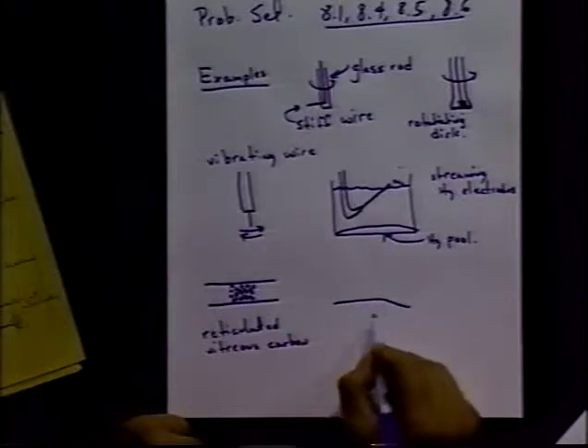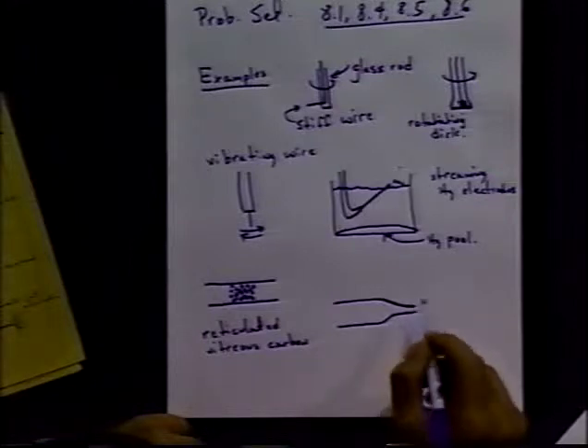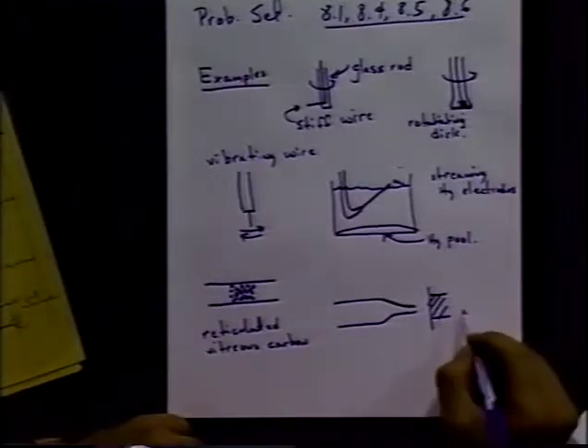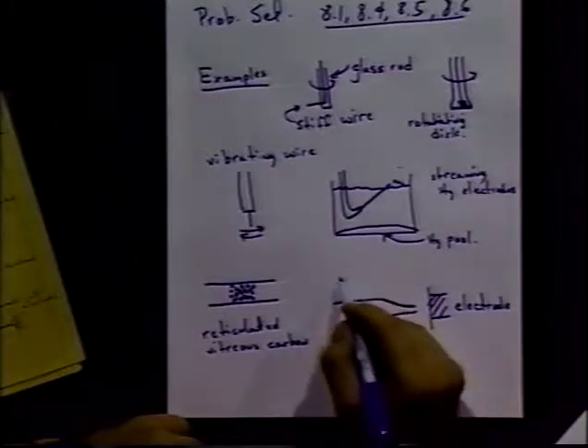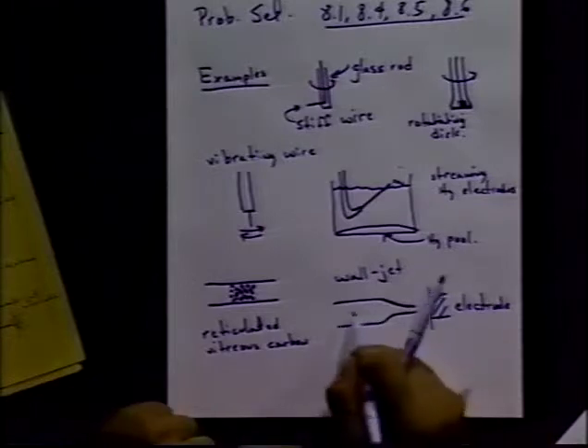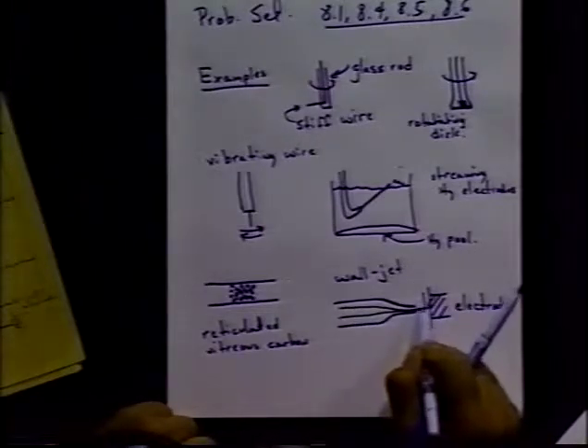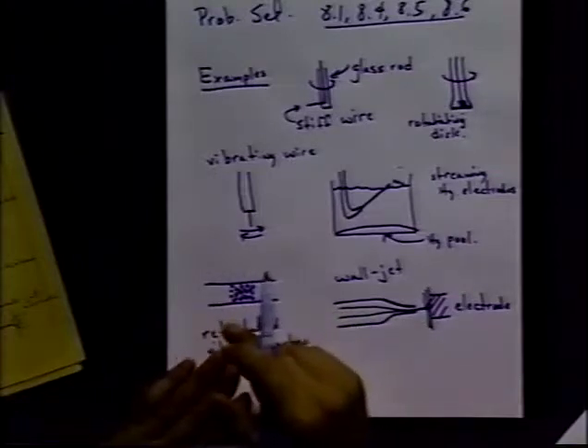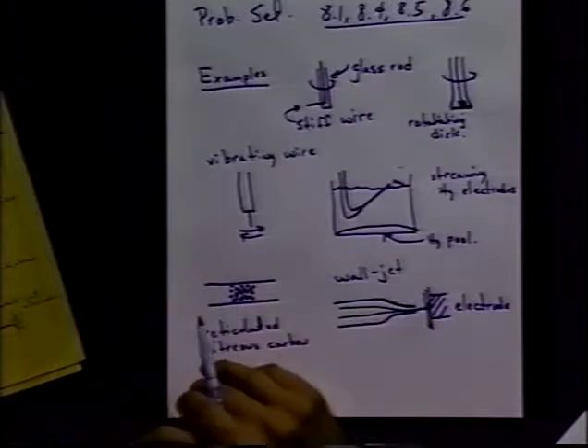Another type of electrode that's actually quite useful is a wall jet electrode. An electrode uses a nozzle and having that nozzle will then impinge upon an electrode. And you can see from the name, the jet of material escaping from the nozzle will impinge on that wall of the electrode and then exit from the sides. And so you get a bathing, a continuous bath of material on that electrode. Now you can either have this happen once or you can recirculate this and so on. Usually this is a kind of a wasteful method, but it actually gives you very reproducible results. So it's useful in that particular case. Sometimes these are set up as detectors, like you can put this on the end of a capillary or chromatography column as act as a detector. Also useful for doing electron transfer kinetic type studies.